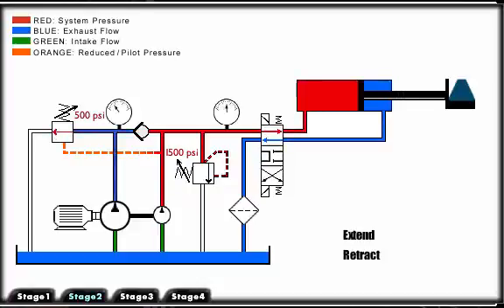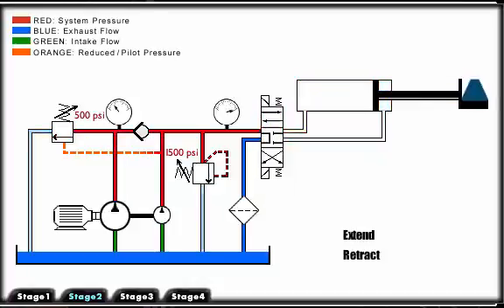At this point, the system pressure increases causing the unloading valve to open. The flow from the large volume pump is directed back to the tank at a minimal pressure. The small volume pump continues to deliver flow for the higher pressure requirement of the work cycle.